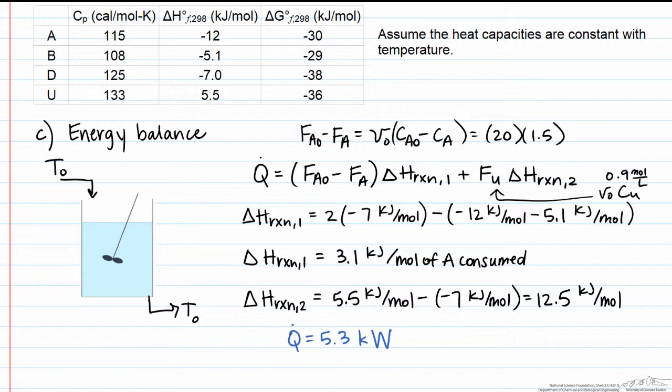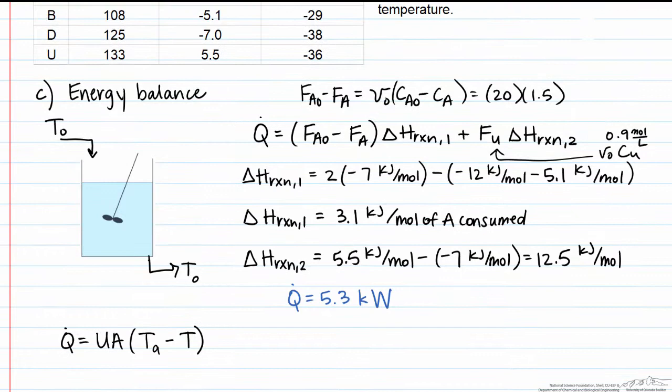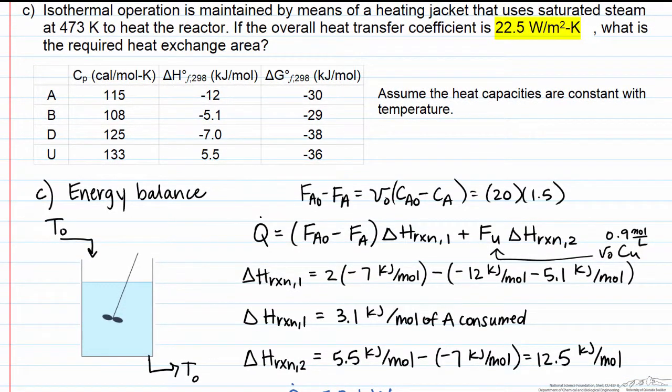We now know how much heat has to be added, and we can relate that to the amount of heat exchange area that we need. The overall rate of heat transfer is equal to an overall heat transfer coefficient times the area that we're trying to solve for for the jacket times the temperature difference across which the heat is being transferred. The overall heat transfer coefficient is 22.5 watts per meter squared kelvin.